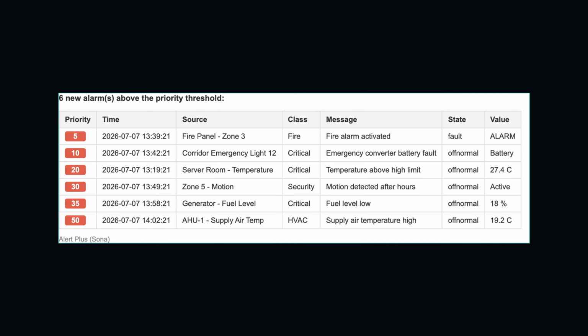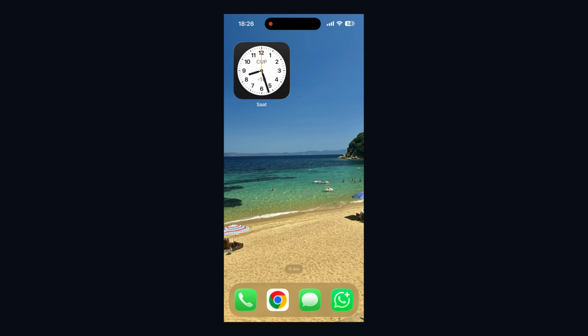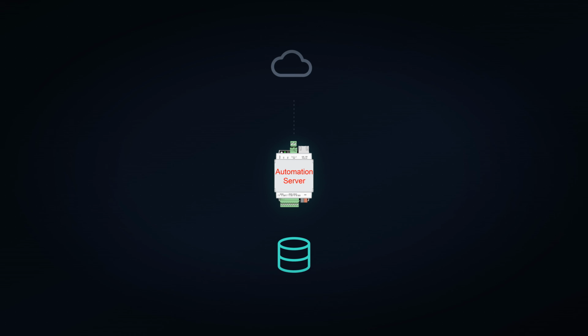Alarms above a defined priority threshold are gathered into a single summary email and sent together, so a separate email is not sent for every alarm. The same notification also reaches the automation server's own mobile app at once, so the responsible person who is off-site is kept informed as well. None of this requires a third-party cloud service. All alarm data and all alarm logic reside on the automation server. Even if the internet or cloud connection is lost, gathering, prioritizing, displaying, and auditing alarms continues without interruption.